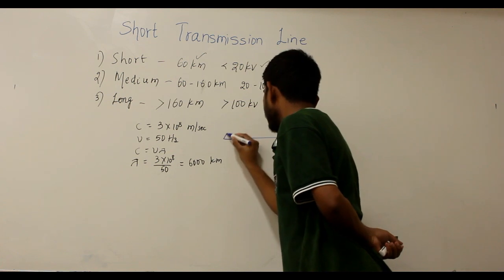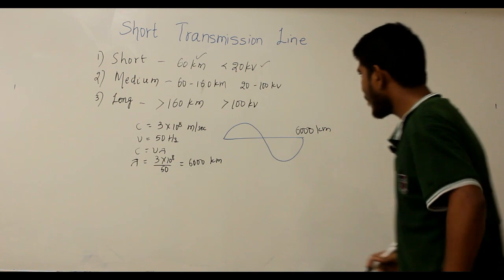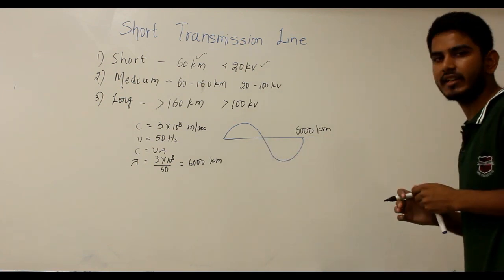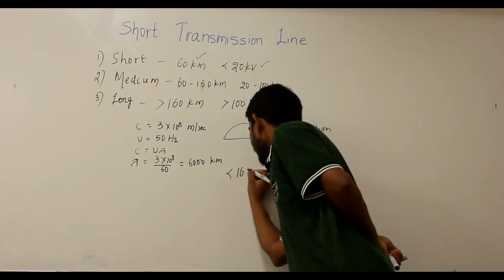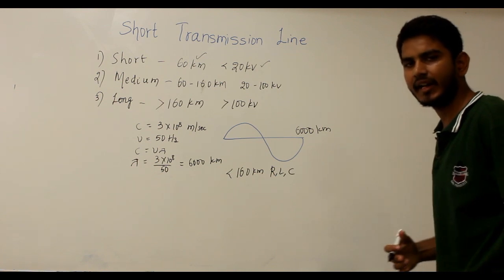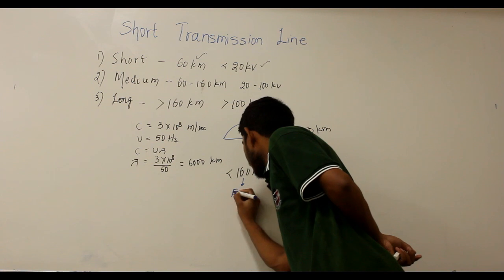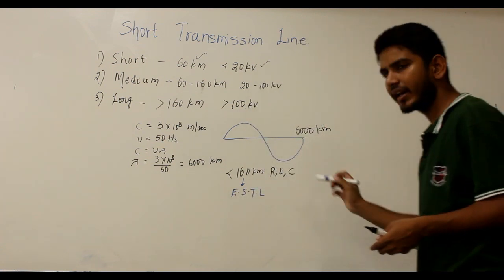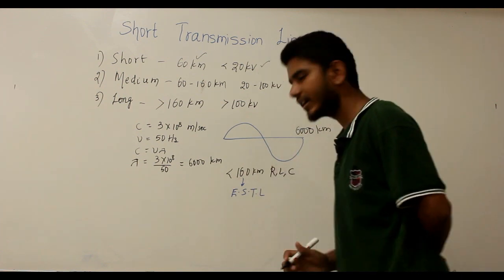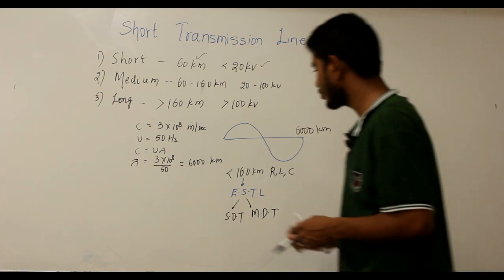So the wavelength of the power being transmitted is 6000 kilometers. Comparing this with the generally used line lengths, those line lengths are very small. For this reason, for transmission lines up to 160 kilometers, the parameters R, L, and C are taken to be lumped or concentrated and not distributed. Such lines below 160 kilometers are called electrically short transmission lines.